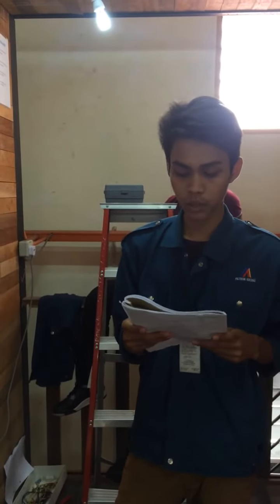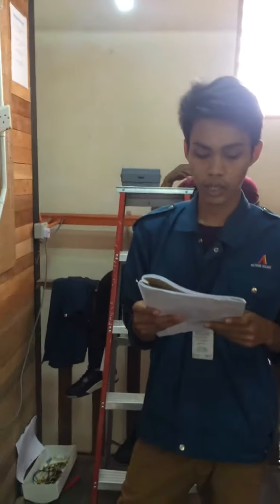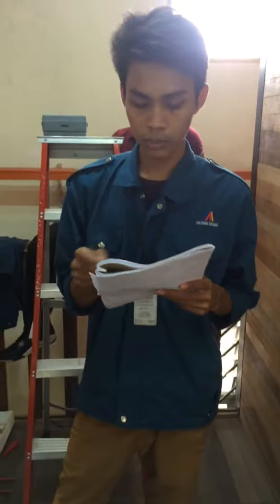First, I will introduce the equipment and the procedure. The equipment: socket tester 1 unit, wire trainer 1 unit. Procedures: first, refer to the testing diagram figure 3.4. Ensure the main power supply has been switched on, including the main switch. Second, put the socket tester on the outlet socket, then turn on the outlet socket. Then record the output from the socket tester display on table 3.4. And last, push the button at the socket tester and record it on the table. Record the result. Let's start the test.